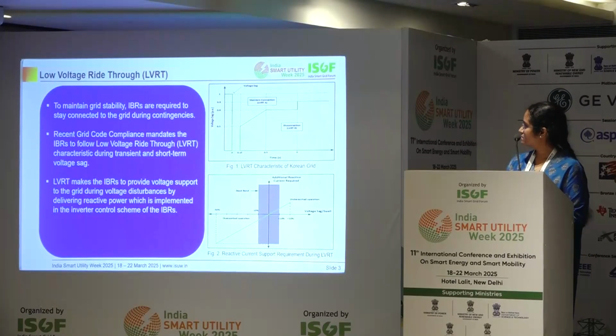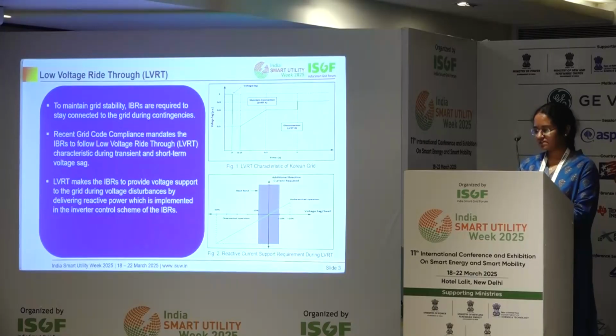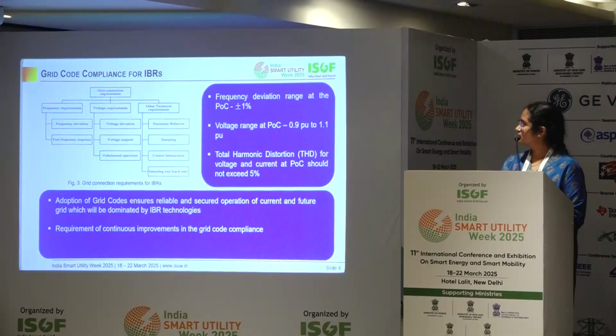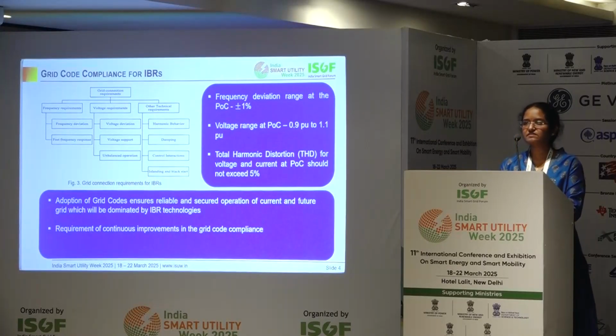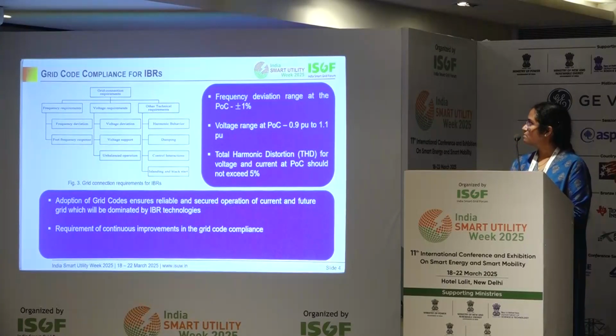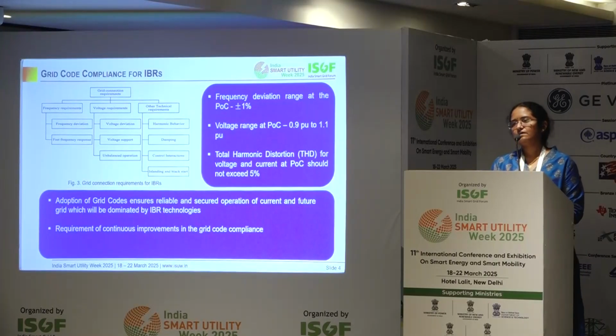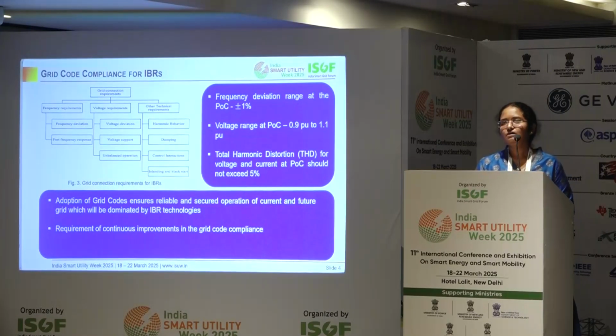Here, if you see, for a voltage variation of 10%, which is under the limit, there won't be any reactive power requirement. But if there is any voltage swell or voltage sag, then it is similar to an over and under excited synchronous motor. The reactive power will be injected into the power grid. These are the grid code compliances given by the CEA regulations. Mostly, the grid code is given for voltage fluctuations, voltage regulations, frequency regulations, reactive power regulations, and harmonic distortion.